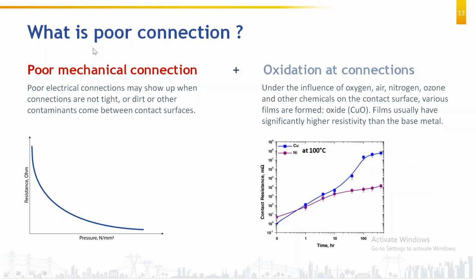Secondly, if you are talking about the connection in a circuit breaker, that means your circuit breaker contacts are not making properly. If a particular 5 square mm area is supposed to be in contact with the other stationary contact, and a lesser amount of area is in contact because of rust, some pitting on the contact, or carbonization on the contact, this also causes quite significant overheating on the terminals.